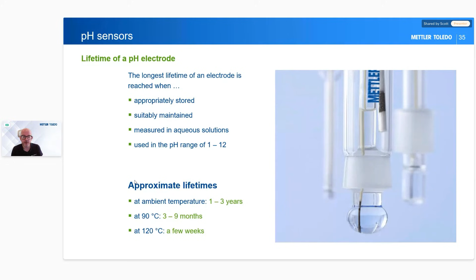The other thing is that if we're using something like high temperatures, then that would degrade it significantly, down to 3 to 9 months, or a few weeks at 120 degrees. The other thing is if we're not doing any of those 4 things above, so we're not storing it properly, we're not maintaining it properly, and we're not measuring aqueous solutions, that will also degrade the electrode life. So things to think about when we're using electrodes is how we use them and how we take care of them.